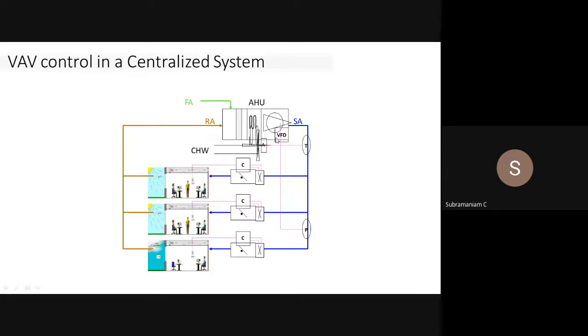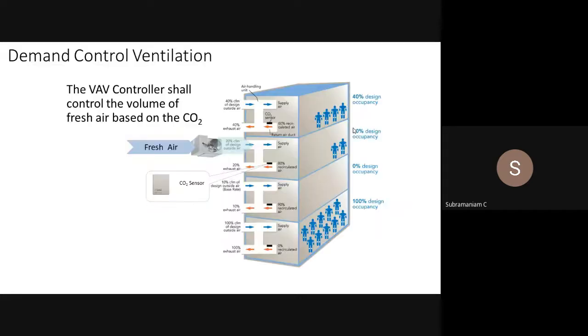And when you are reducing the fan speed by 50%, for example, your energy consumption is cubed. If your speed is getting reduced by 0.5, your energy consumption is 0.5 into 0.5 into 0.5. That is 0.125, 12.5% for a 50% reduction in speed. So this is as per the fan law, which you have learned in fluid mechanics. So whatever you have learned in your college will come handy for energy calculation, energy saving. If somebody is becoming an energy auditor, all this will be useful in that calculation part.